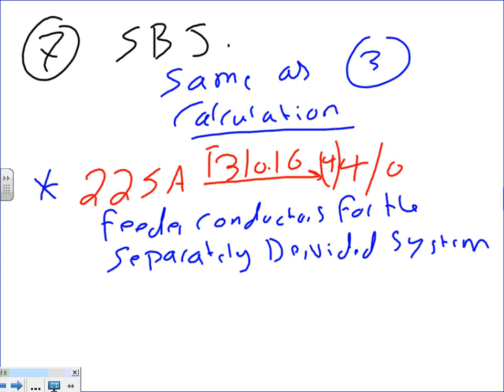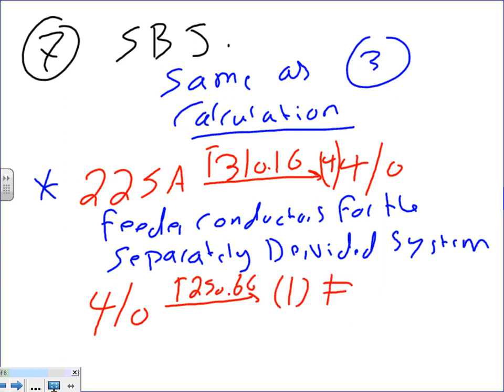The next thing, guys, the next thing you need to do is just take the 4-aught and take this one to table 250.66. I don't have it right here. What's, Spencer? What's, Holly? Number 2. How many? 1 conductor number 2. This one, the one that you guys are going to bond the neutral of the separately derived system to the grounding bar inside the panel or inside the transformer. Doesn't matter. You can bond them inside the transformer or you can bond them inside the panel. So same as number 3, DJ, it's not same as in like the calculation, the answer is the same. The calculation is the same way, right?